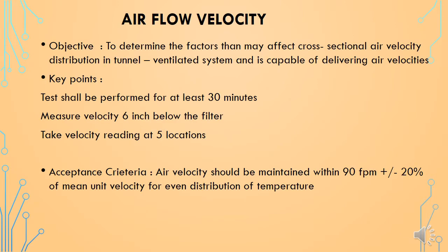Now we will see the first test: air velocity check. The purpose or objective of this test is to check the factors that affect cross-sectional air velocity distribution in tunnel ventilated systems. This air velocity check is done to ensure maintenance of continuous laminarity of HEPA filters installed in the tunnel or oven. To perform this test, we need a hot wire anemometer.